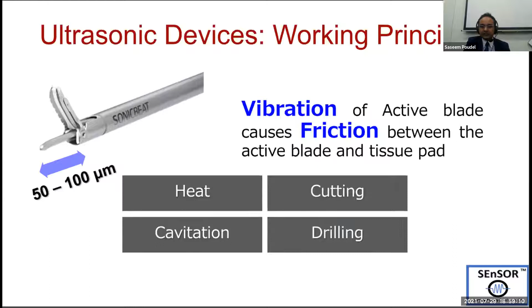Basically, there are two settings you use in ultrasonic devices, and a lot of these machines can control more than two settings. There are maximum and minimum settings, and you can also make minute changes. What you are controlling is the distance the active blade travels in this back and forth movement. In the max setting, the active blade protrudes more, so it has a longer stroke, and that makes cutting easier.